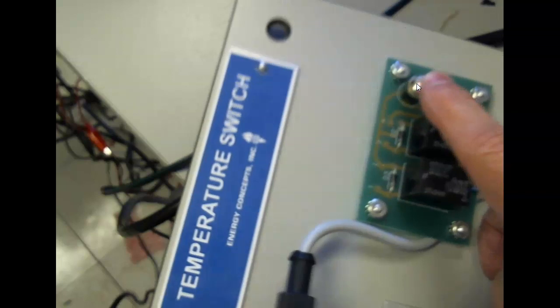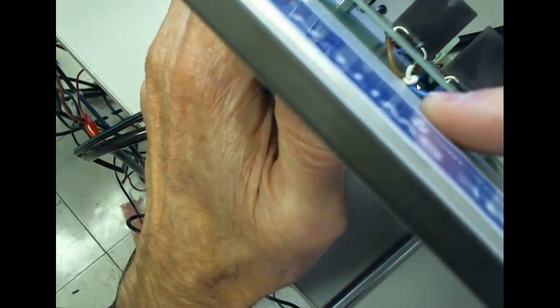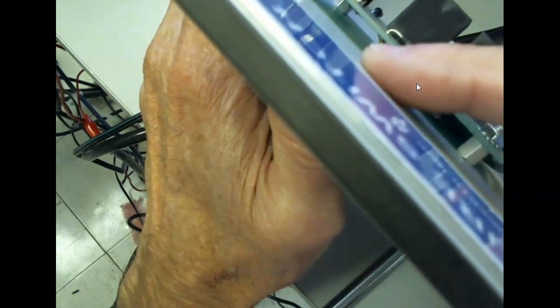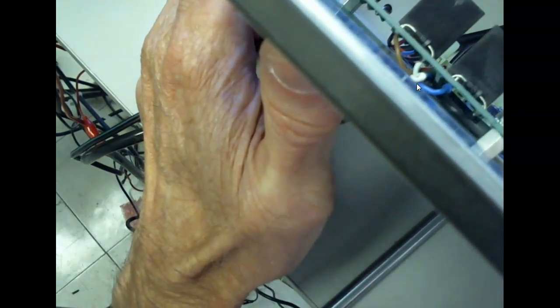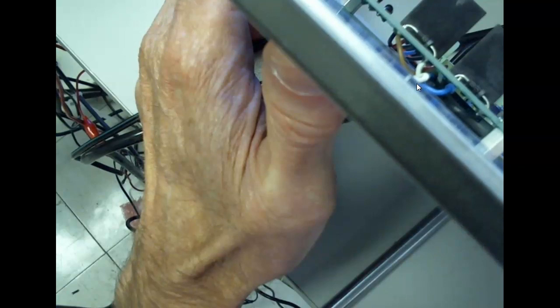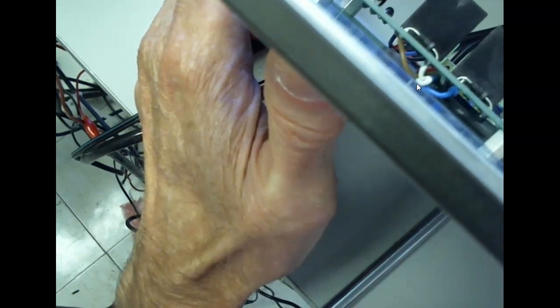And then on the back, the sensor is hooked up to this guy. If you look at the back, you can actually see the brown and blue and then the white and black. So brown and blue are what? Oh, y'all can't see? Yeah, there we go. That's a pretty good shot, ain't it? Except you can't really see the black, but we can see the white. Blue and brown are our power, right? Then white would normally be the normally closed, and the black would be the normally open. But there's always that, right?